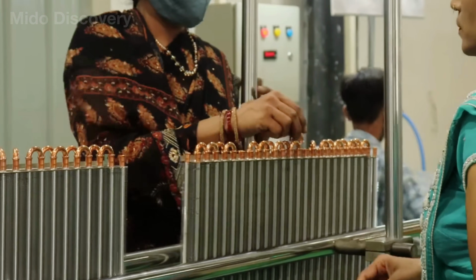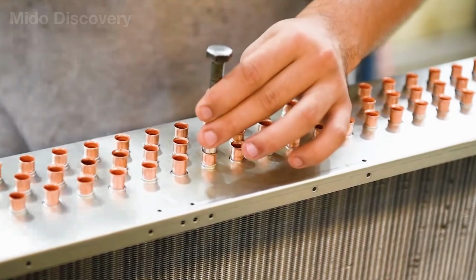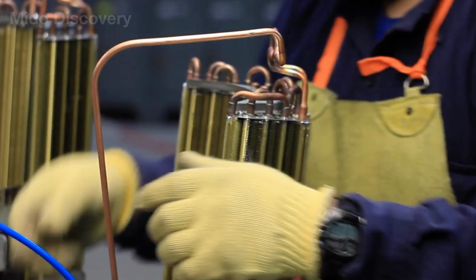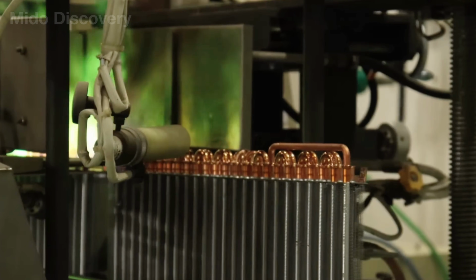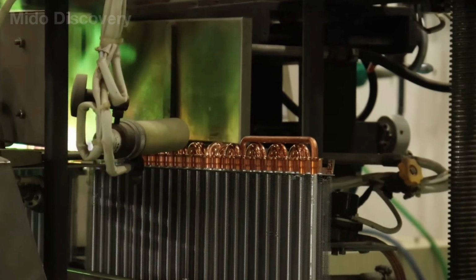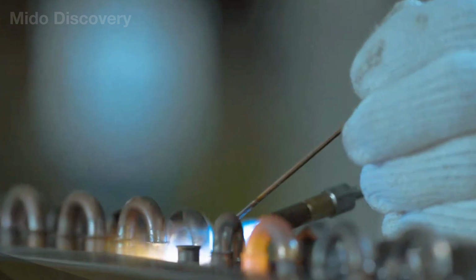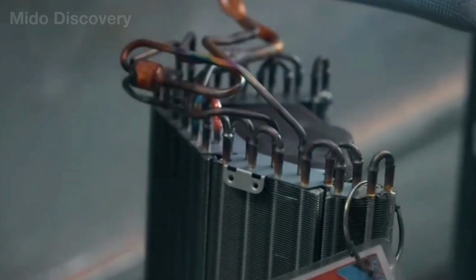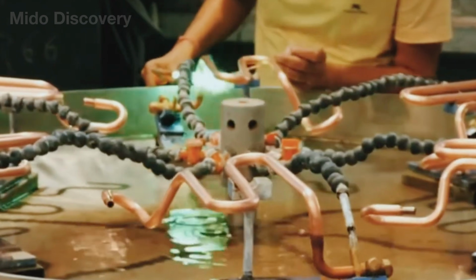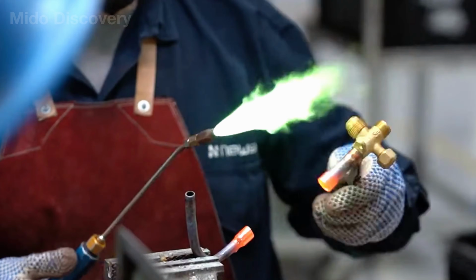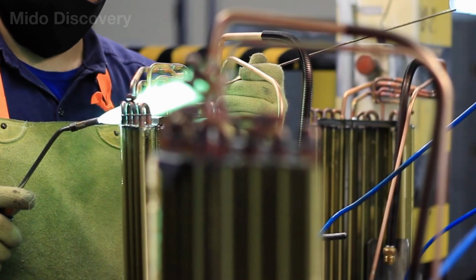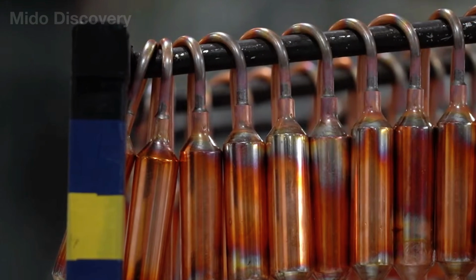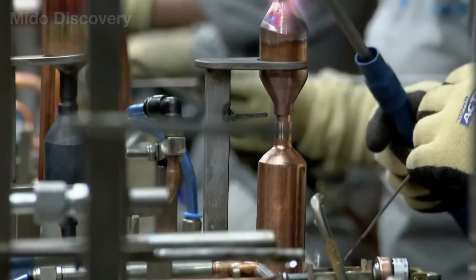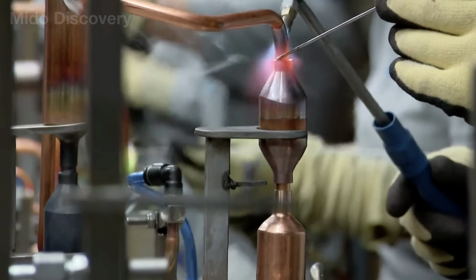Once the copper tubes have been threaded through the aluminum fins and mechanically expanded into place, workers begin sealing the refrigerant circuit. Each tube end is cleaned, carefully aligned, and heated with a torch. When the copper reaches the proper temperature, the brazing alloy melts and is drawn into the joint by capillary action, forming a strong, airtight bond as it cools. During heating, nitrogen may be fed slowly through the tubing. This protective flow helps prevent oxide from forming inside, tiny flakes that could later break loose, travel through the system, and create blockages. But a clean, polished joint is not always a leak-free one.